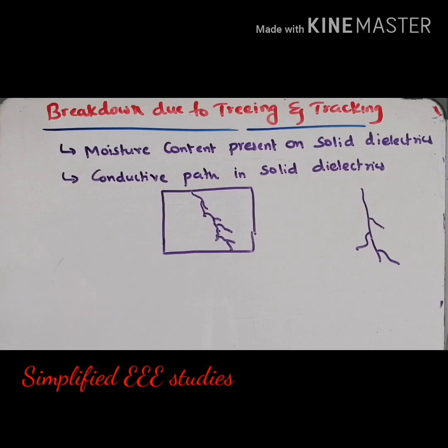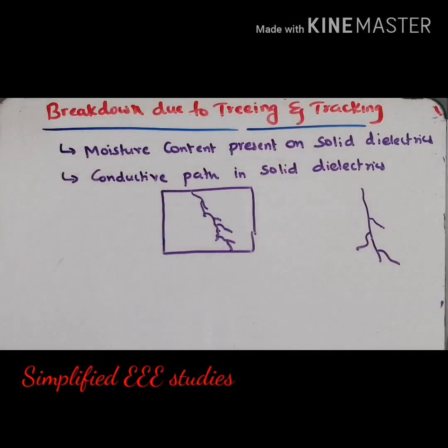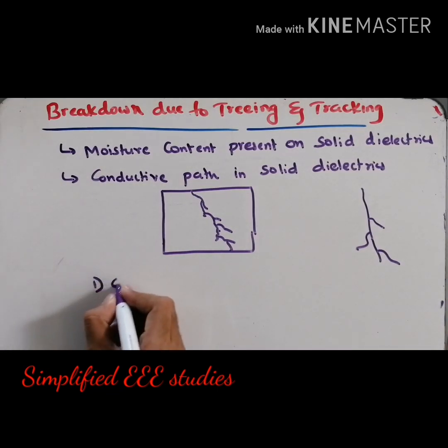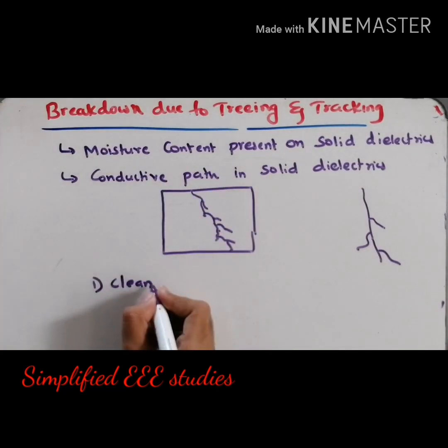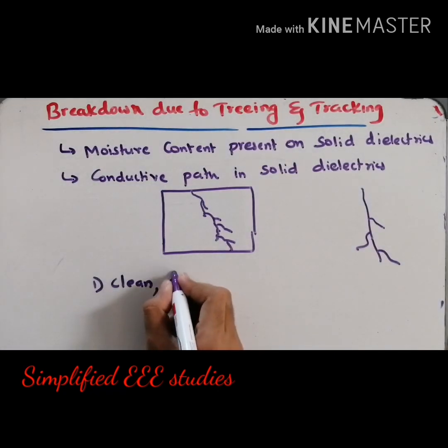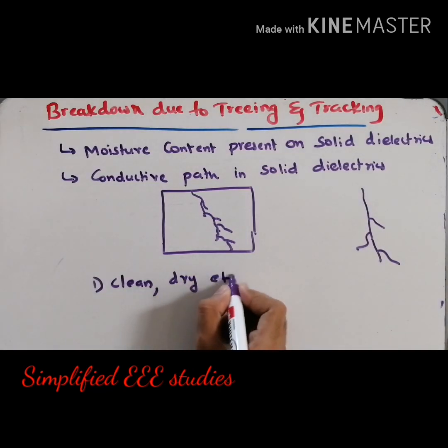How to overcome this phenomenon? How to get rid of treeing and tracking? There are several methods. The first method is to clean the solid dielectric material frequently — provide cleanliness. The second method is to keep the solid dielectric material dry. These are the basic precautions you can take to protect the solid dielectric material against treeing and tracking.